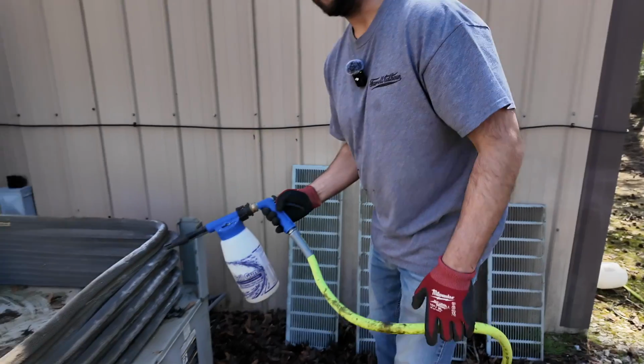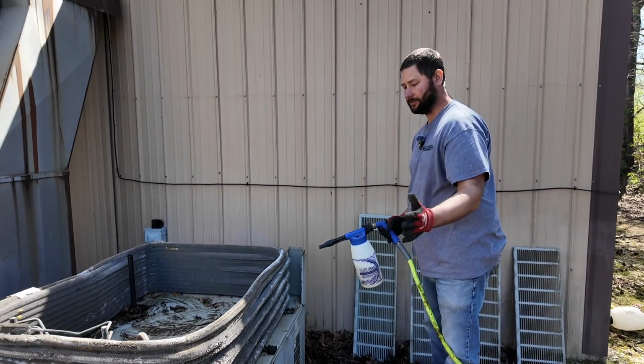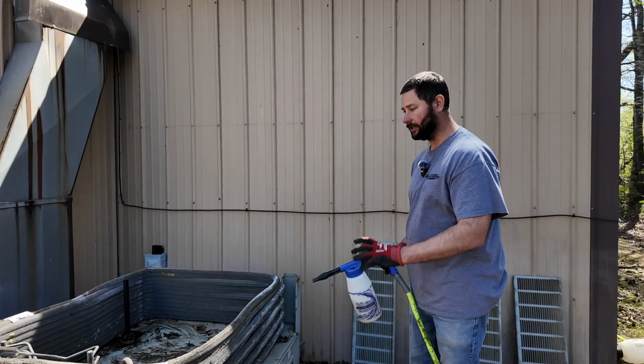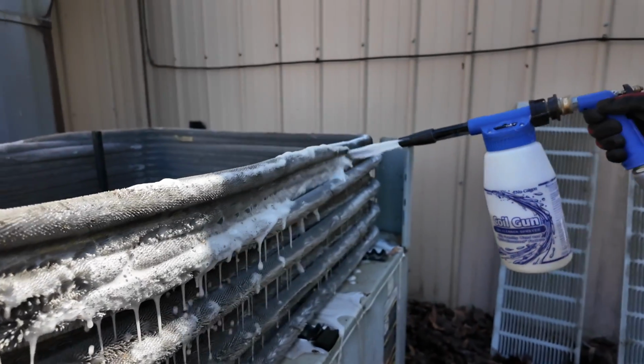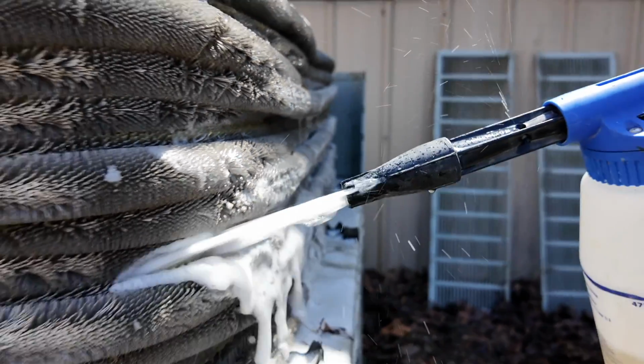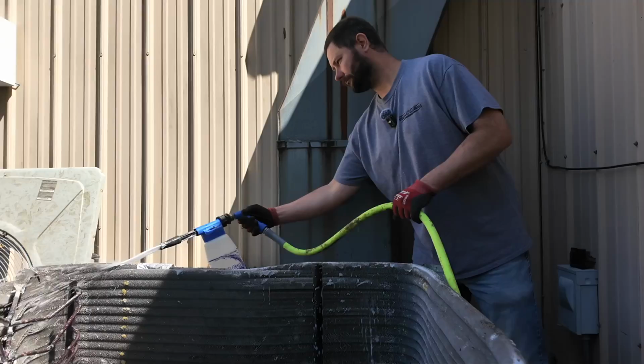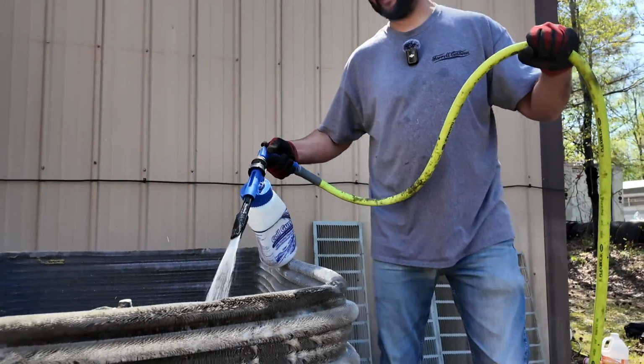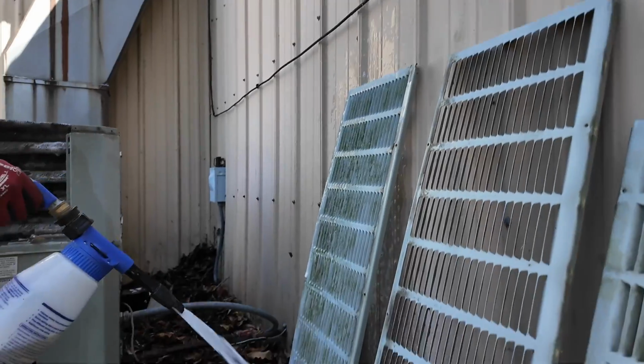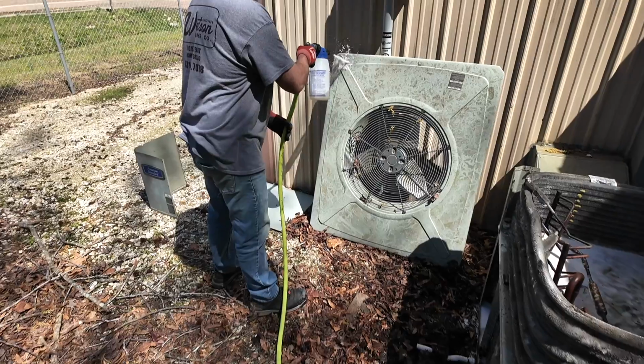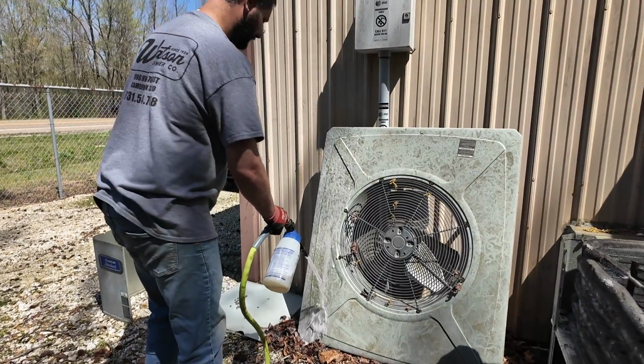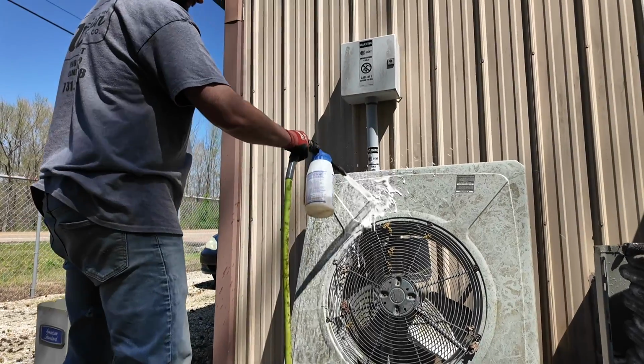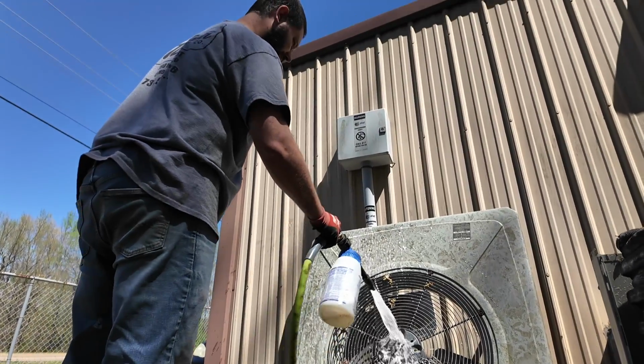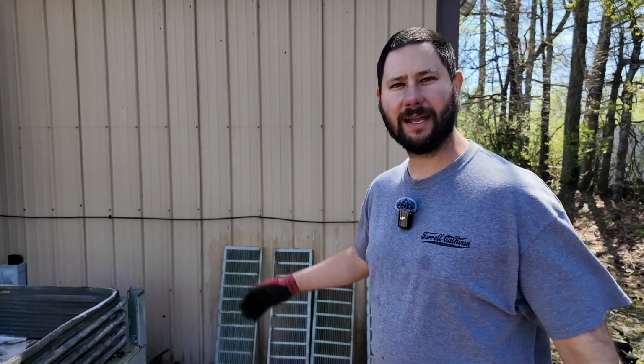Let's start with the coil. I'm gonna go from the outside and the inside. I'm gonna spray both ways just to make sure that I get a good, clean coil. We got our coil cleaner on the condenser coil, our guards or our grills, and the top. We're gonna let it set 3 to 5 minutes, come back and wash it off.